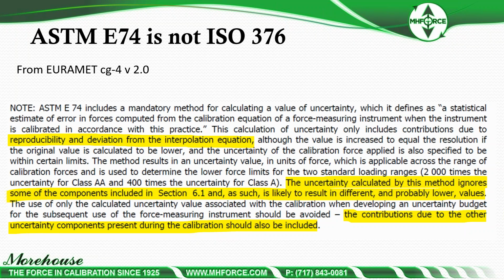It gives a nice write-up here. The calculation of uncertainty only includes contributions due to reproducibility and deviation from the interpolation equation. The uncertainty calculated by this method, they're talking about ASTM, ignores some of the components included in section 6.1. As such, it is likely to result in different and probably lower values. And then the contributors due to the other uncertainty components present during the calibration should also be included. Recommendation, it's basically saying that ASTM is missing several things that ISO does have as far as uncertainty.